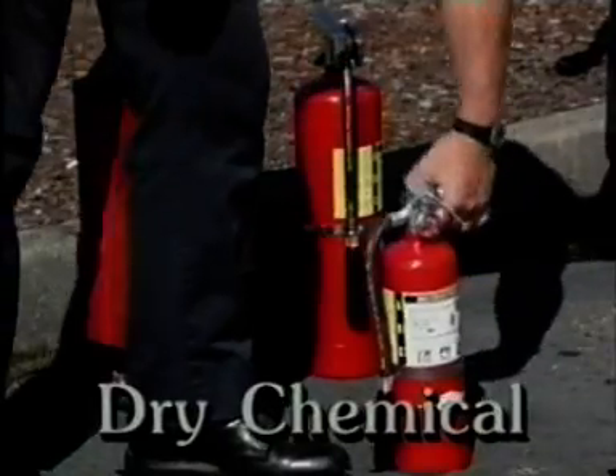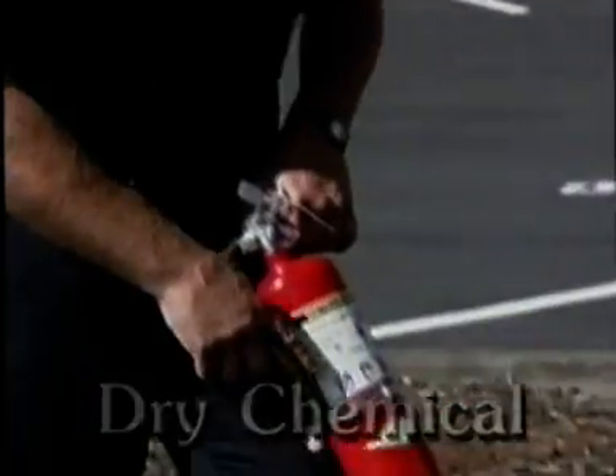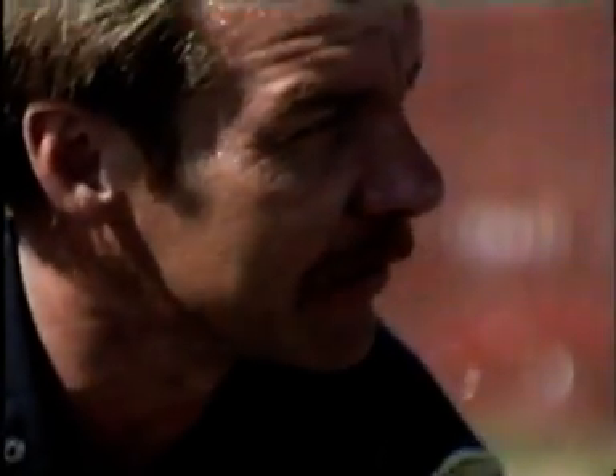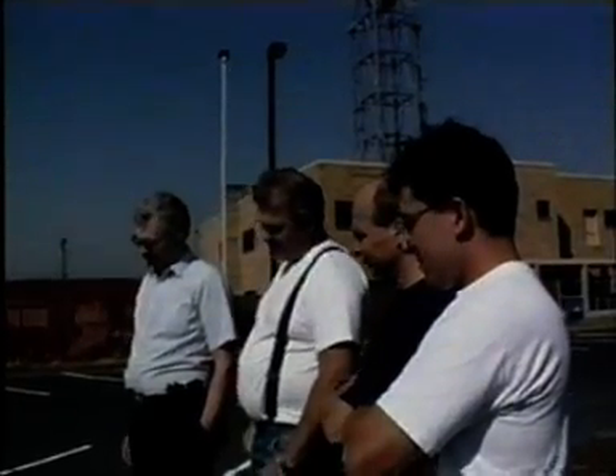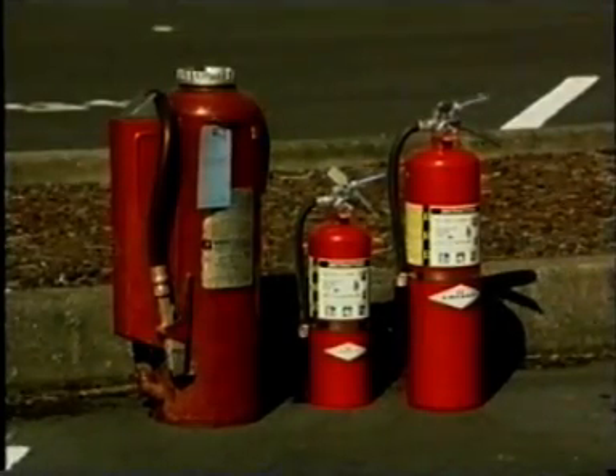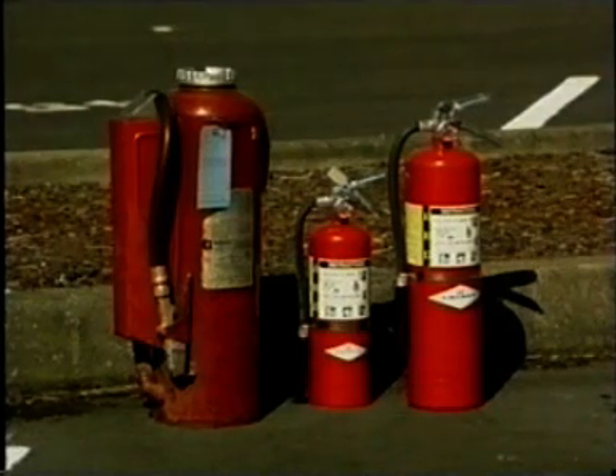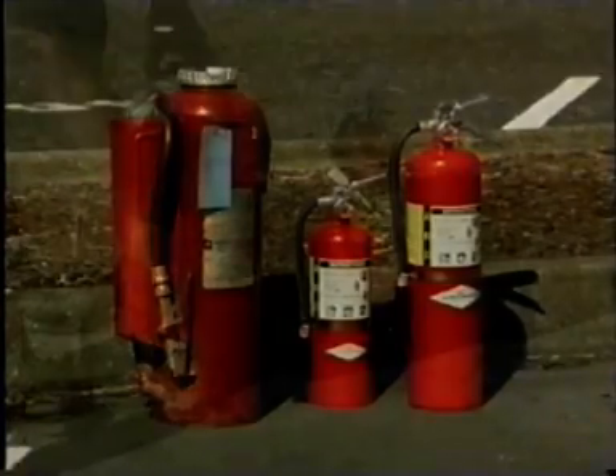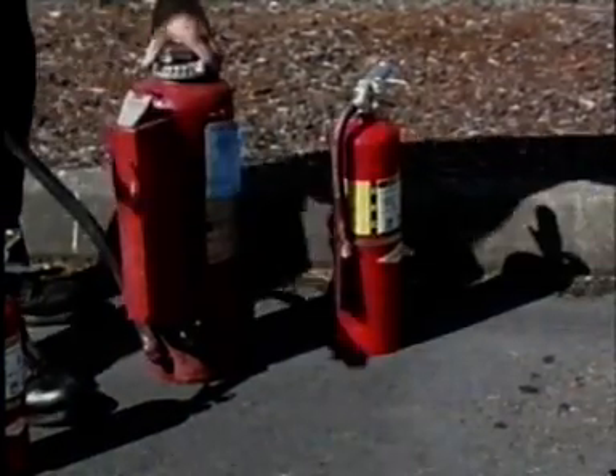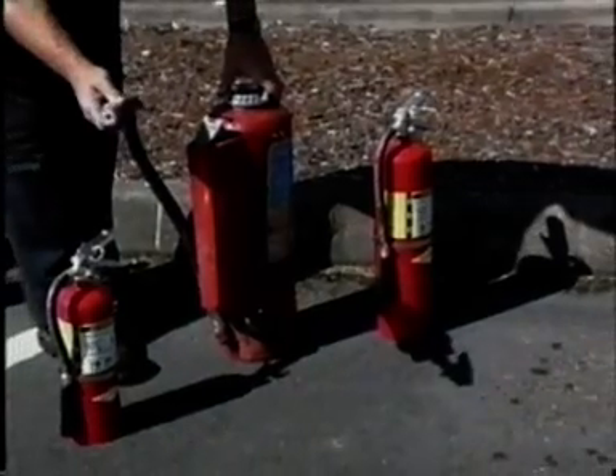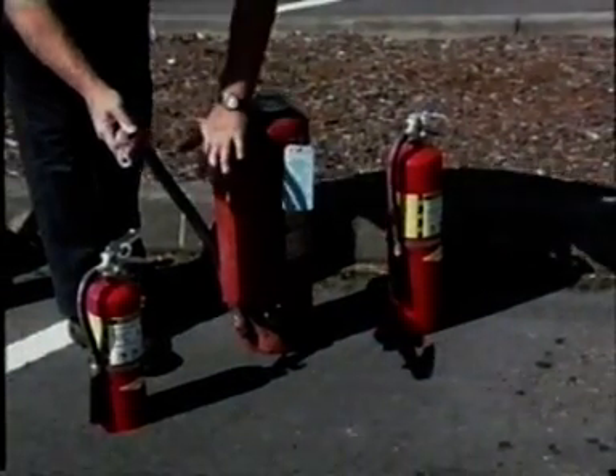Dry chemical extinguishers are the most common portable fire extinguishers in use today. There are two basic types: ordinary dry chemical extinguishers, which are for Class B and Class C fires, and multi-purpose dry chemical extinguishers, which are rated for Class A, B, and C fires. Whichever type you have, the operation of all dry chemical extinguishers is basically the same.